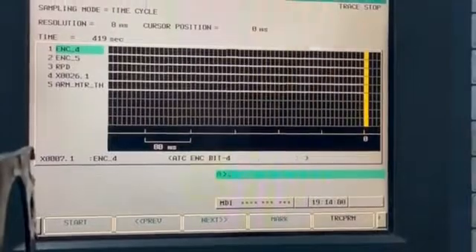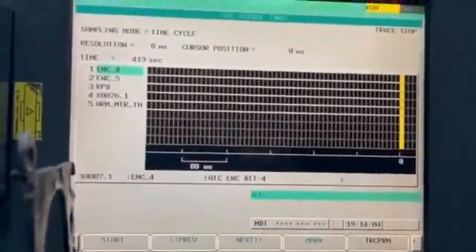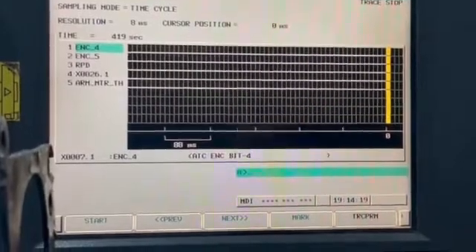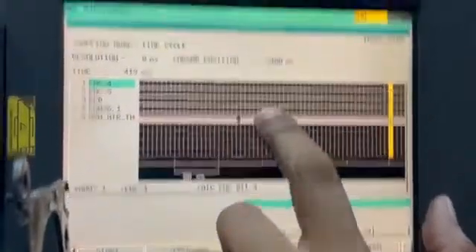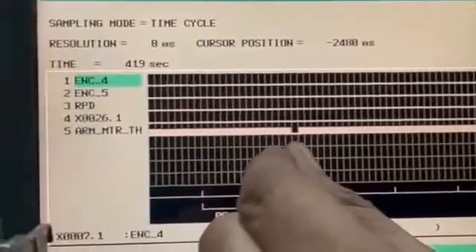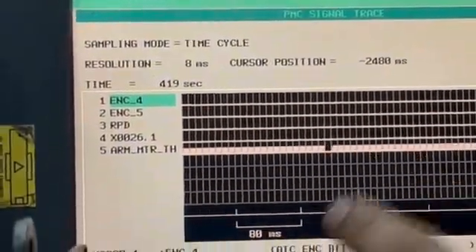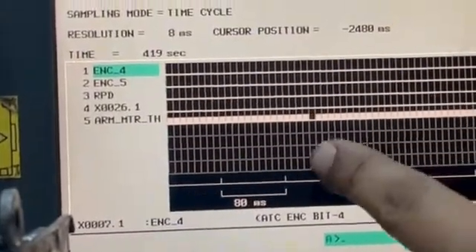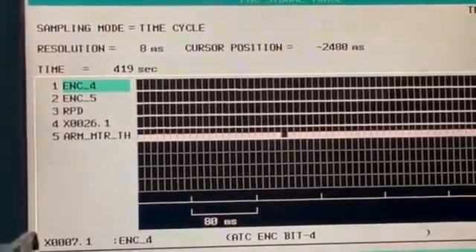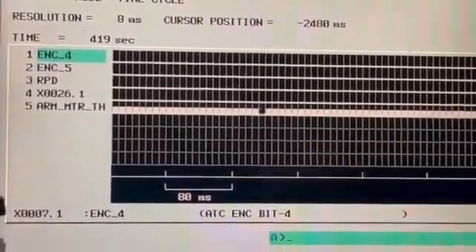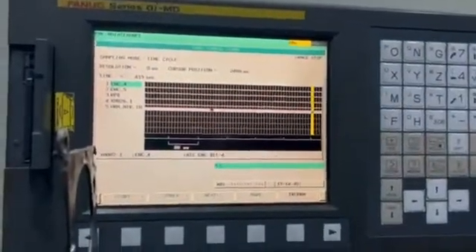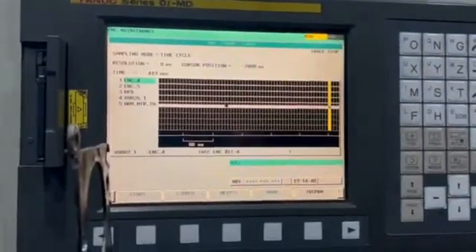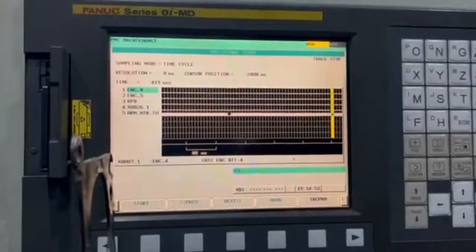Now we will go to the trace function and we will see how this event was recorded in the oscilloscope. See, we are looking for the signal. Look, this is the break in the signal. For this one block, which is equivalent to 8 milliseconds, the signal was low. The oscilloscope has recorded this event. It is a very useful function because sometimes there is a problem coming and the machine is giving an alarm and we are not able to diagnose it properly. With the trace function, we can monitor all the signals and all the outputs in this CNC machine. Thank you.